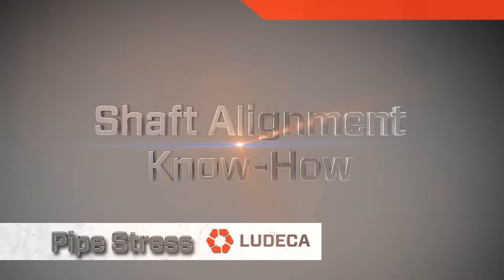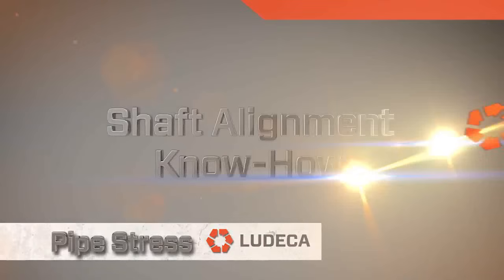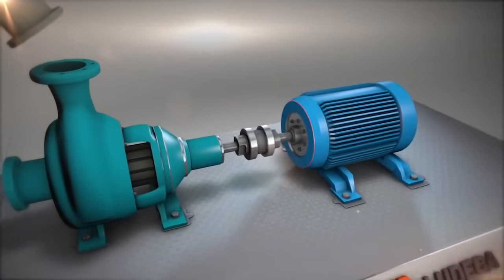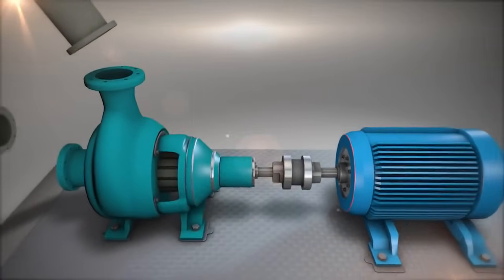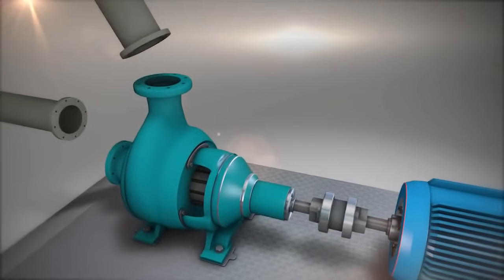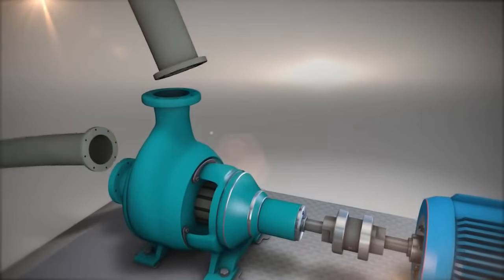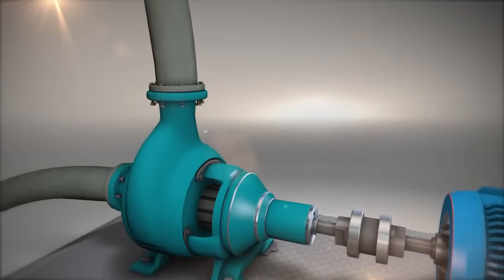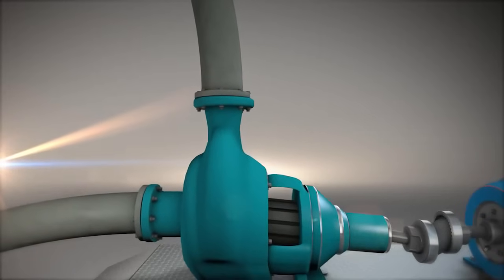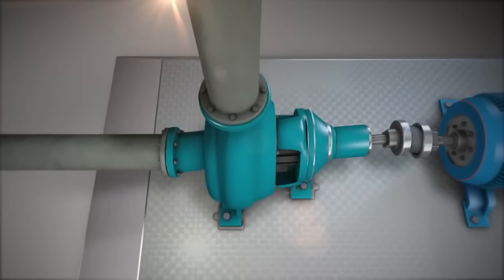Shaft alignment know-how: Pipe stress. Often during pump installations, pipe and pump flanges are not in alignment. When mated together, the pipe stress pulls on the pump flange. This forces the frame of the pump to distort vertically and or horizontally.